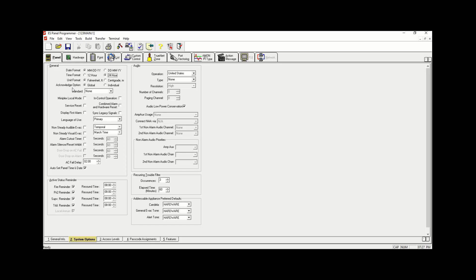Under the Acknowledge option we have two choices: Global and Individual. The difference is that with Individual, upon any fire alarm, trouble alarm, or supervisory event, you have to go and acknowledge each and every single annunciator or node individually. With Global, you can acknowledge any of them from any location.